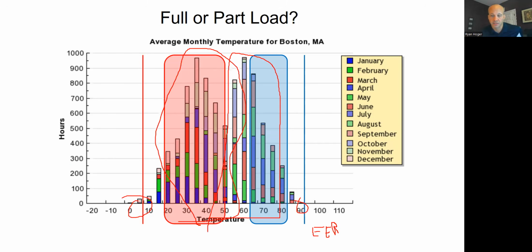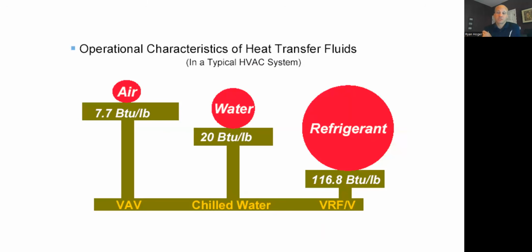Cooling days, heating days. All right, so VRF systems, we're going to move the energy around the building with refrigerant instead of moving around with ductwork. So generally speaking, no ductwork and not even water, which would be boilers and chillers. This is just to give you an idea, give you an example. This is how much energy I can move through air, 7.7 BTUs of energy for every pound of air. If I go to water systems, I'm averaging 20. And if I go to refrigerant systems, 117.